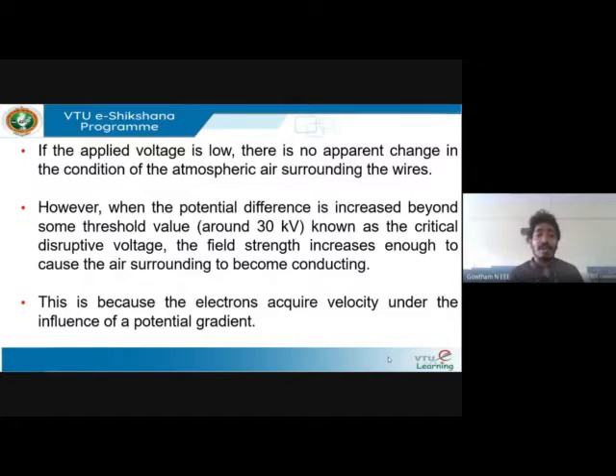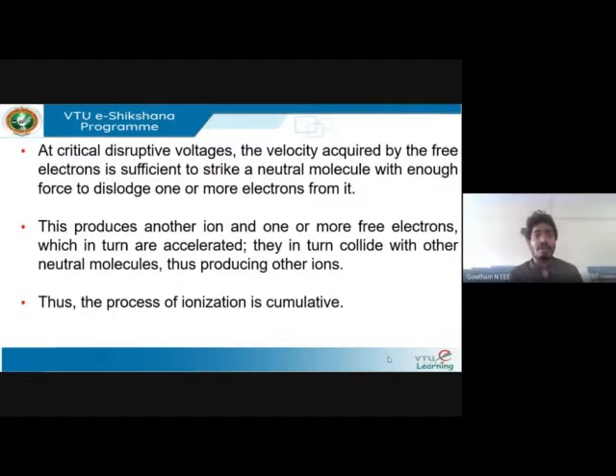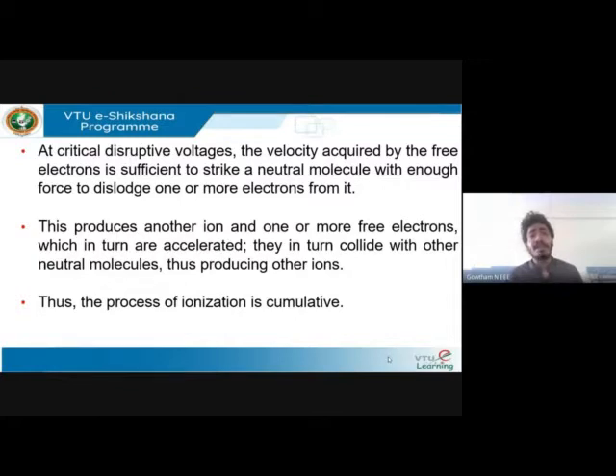Electrons acquire velocity under the influence of the potential gradient, which is the stress. At critical disruptive voltage, the velocity acquired by free electrons is sufficient to strike neutral molecules. Because the voltage is increasing, the stress is more, and more electrons ooze out or get dislodged from the conductor. They flow through the surrounding air medium, collisions take place producing ions — and that is why corona is mainly a phenomenon of ionization.